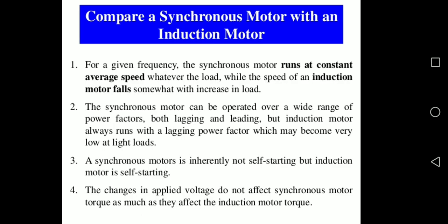The synchronous motor can operate over a wide range of power factors, lagging, leading, and unity, but induction machines only operate at lagging power factor conditions. The third point: a synchronous motor is inherently not self-starting, but an induction motor is a self-starting machine. So as we said, the third point is very important. The synchronous machine starting torque is zero, but in induction machines starting torque is available.